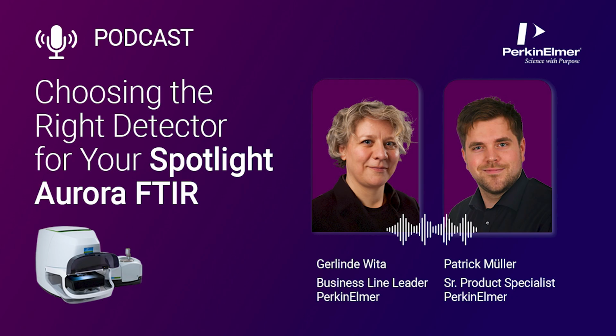Because with liquid nitrogen, you have the cool down time of your detector when you fill it. Both the thermoelectrically cooled MCT and the InGaAs detector do not have this problem.